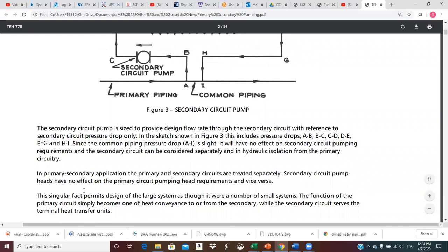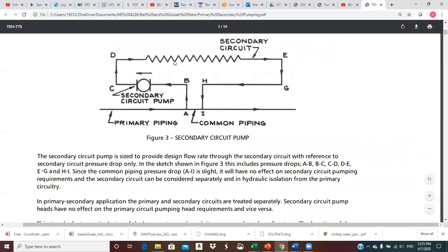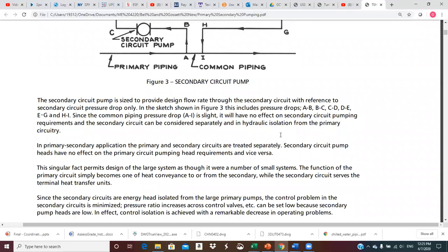This singular fact permits design of the large system as though it were a number of small systems. The function of the primary circuit simply becomes one of heat conveyance to or from the secondary, while the secondary circuit serves the terminal heat transfer units. Since secondary circuits are energy-head isolated from the large primary pumps, the control problem in the secondary circuit is minimized. Pressure ratio increases across control valves are kept low because secondary pump heads are low — control isolation is achieved with a remarkable decrease in operating problems.